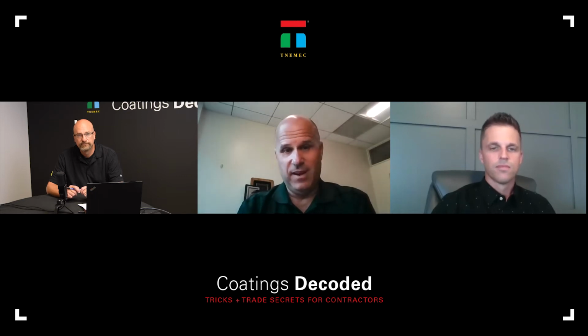Conversely, if I have a material that has a low thermal conductivity and can go on thicker, then I have the best situation and I need fewer coats to get to a higher thermal benefit. So Andy, it sounds like for a contractor approaching an insulative coating project, the K value of each product that might be considered and quoted on that project is going to be really critical, because a lower K value means a more efficient insulative product and potentially fewer coats than something at a higher K value.